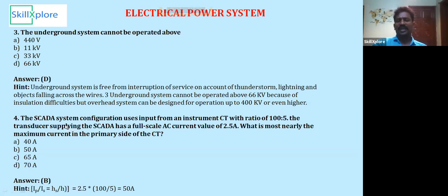The SCADA system configuration uses input from an instrument current transformer with a ratio of 100:5. The transducer supplying the SCADA has a full scale AC current value of 2.5 amps. What is most nearly the maximum current on the primary side of the current transformer?